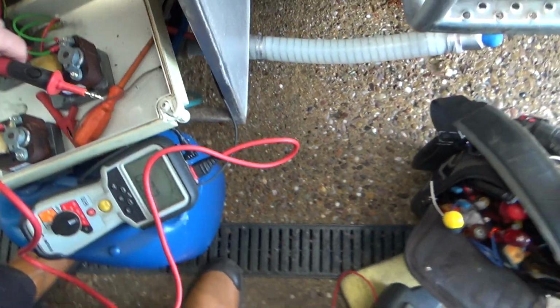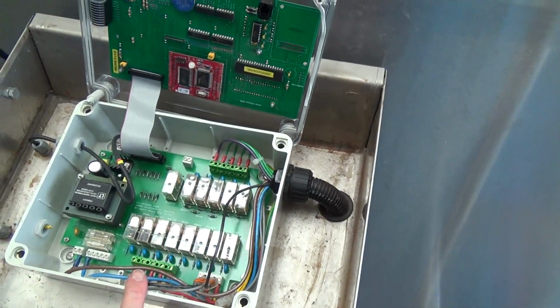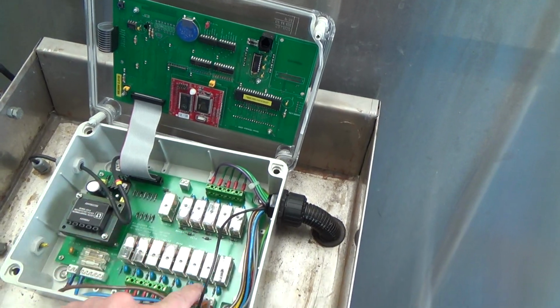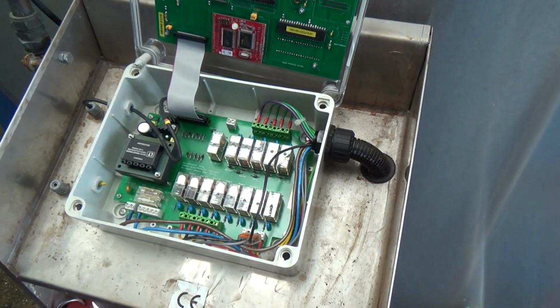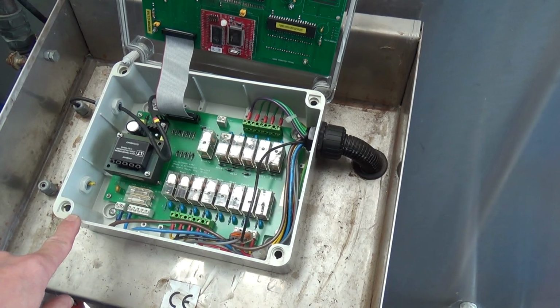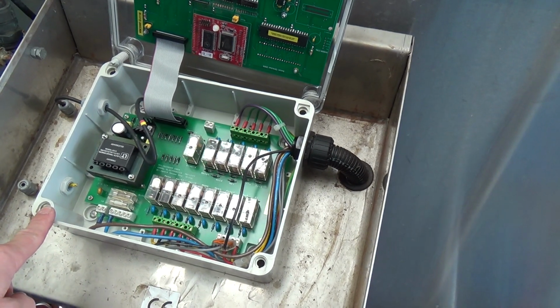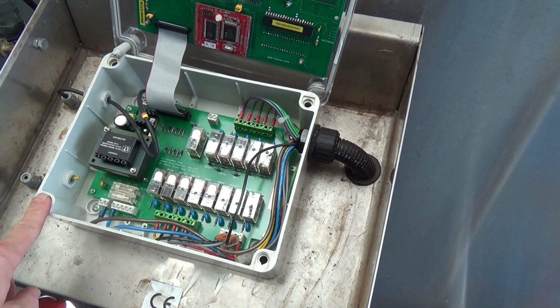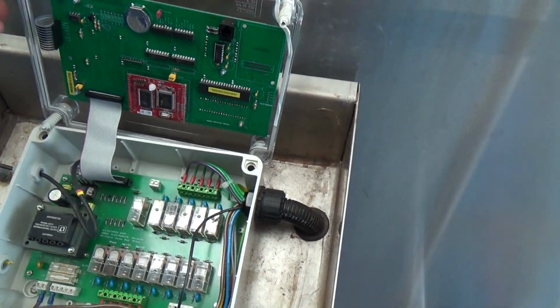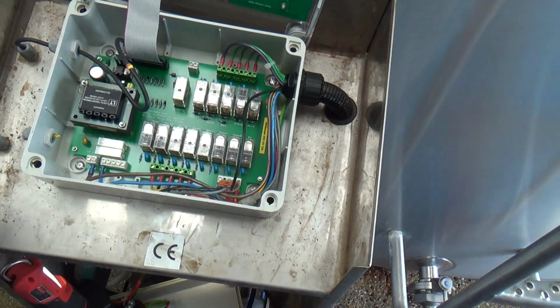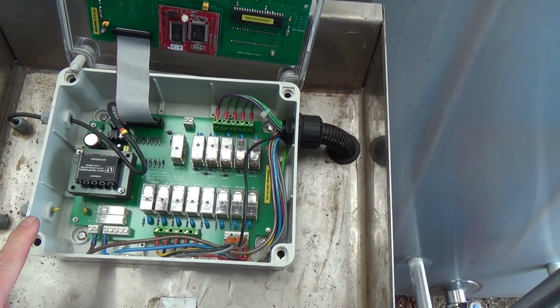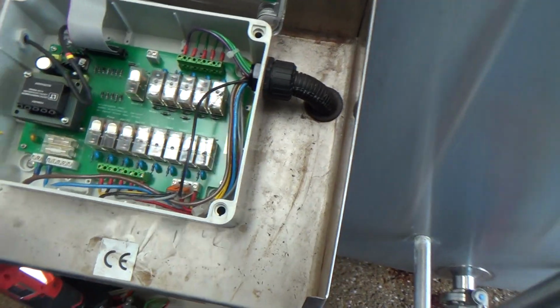Yeah. So it's looking like that signal we're now getting is the booster pump and the 2 compressor feeds, which is to be expected. So we need to go and check the booster pump. That's the only thing that would be on during the wash. The compressors wouldn't come on in the wash. If it was one of the, say, the solenoid coils, the problem would be in cooling mode.